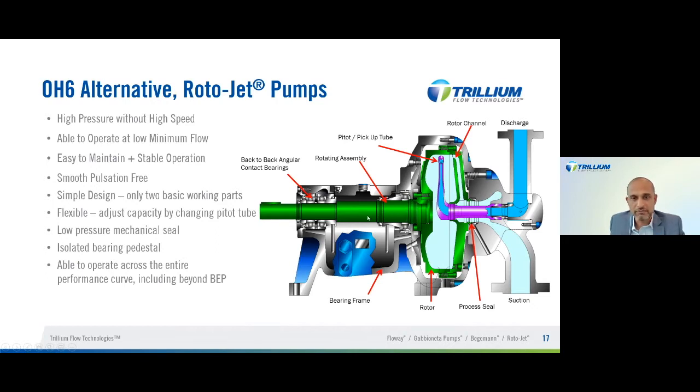And to achieve the speed we require, this rotor assembly is connected to an external gearbox, which has different gear ratios to change the pressure, and that is connected to a standard 2-pole or 4-pole motor, which is very similar or exactly the same as what you would use in a traditional centrifugal pump. And here you would also notice it's a standard external gearbox, which is not force lubricated. We have ball bearing for radial and double row for angular contact for thrust.